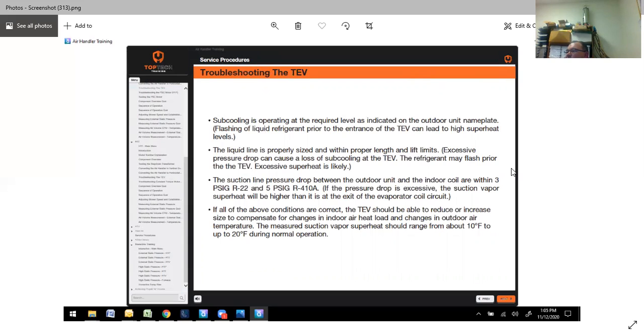The suction pressure drop between the outdoor coil and the indoor coil should be within 3 psig on R22 or 5 on R410A. If the pressure drop is excessive, the suction vapor superheat will be higher than it is at the exit of the evaporator coil. If all the above conditions are met, the TEV should be able to reduce or increase the size to compensate for changes in the indoor heat load and changes in the outdoor air temperature. The measured suction vapor superheat range should be about 10 degrees Fahrenheit up to 20 degrees during normal operation.